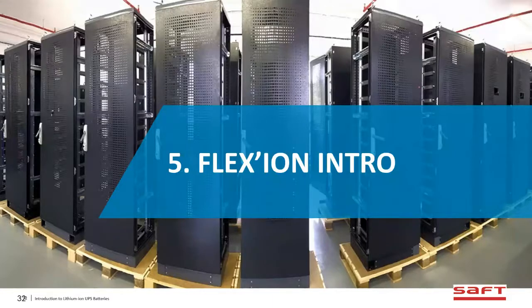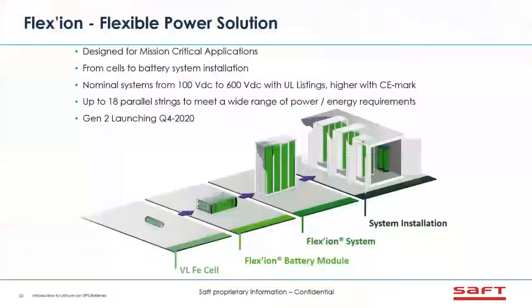Quick introduction to lithium, our product line for UPS. So Flexion, it's a flexible power solution. It's designed for mission critical applications. Everything is done from Saft, from the cells through the full battery installation or battery assembly. We can build batteries from 100 volts to 600 volts with our UL listing, and can go even higher with the CE mark. We can do up to 18 parallel strings to meet a huge range of power and energy requirements. To give an example of that full 18 strings, that's roughly 2.5 megawatts of power under one controller.